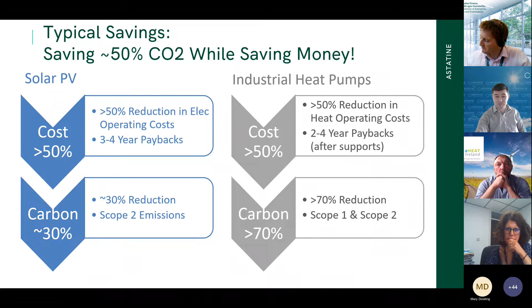Just in terms of getting into specific projects, when we go on a site, this is what we're looking for. We're looking for places with low temperature heat that the heat pump can use as a source. So on dairy facilities, this would typically be 30 to 50 degrees waste heat that's not being used. And we're looking for places to use that waste heat on those sites to replace oil or gas that's currently being used by a boiler.